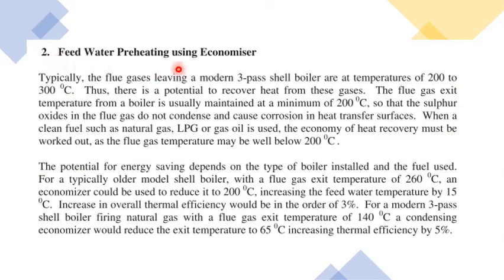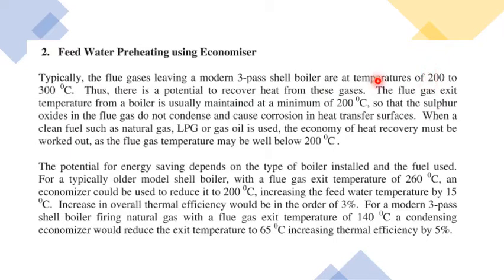The second point is feed water preheating using an economizer. The economizer is equipment used to preheat the feed water entering the boiler using waste heat from flue gas. For example, if the target is to keep flue gas below 200°C but the temperature is 300°C, the extra 100°C can be used to preheat the feed water.